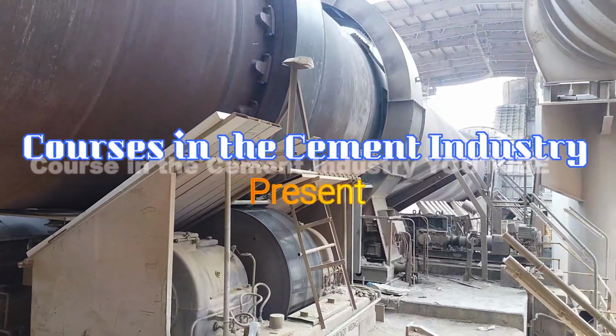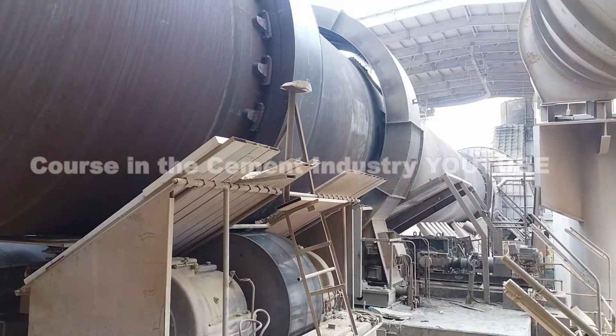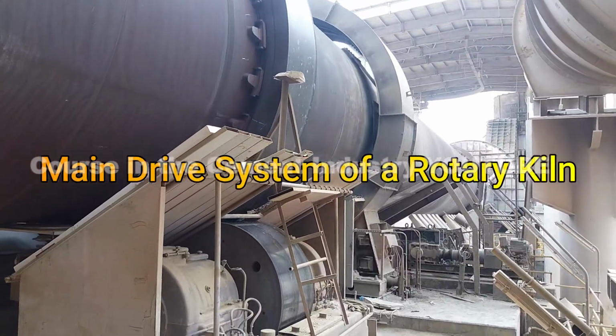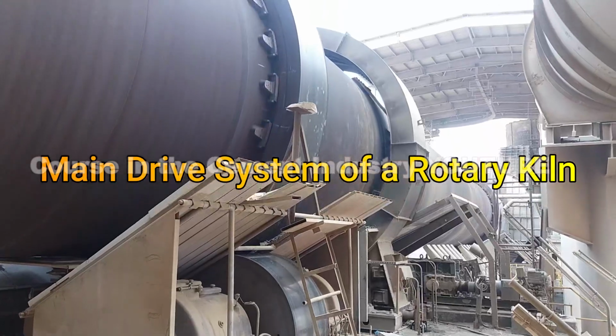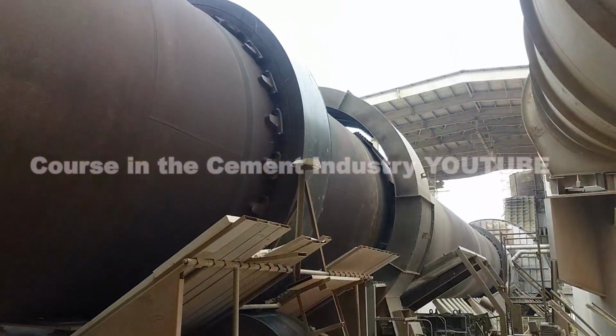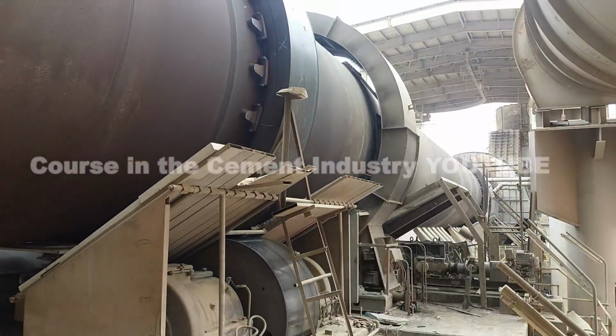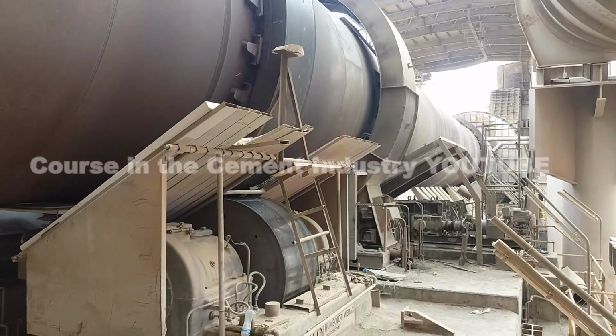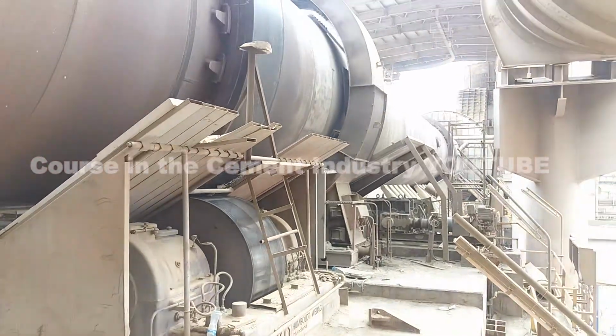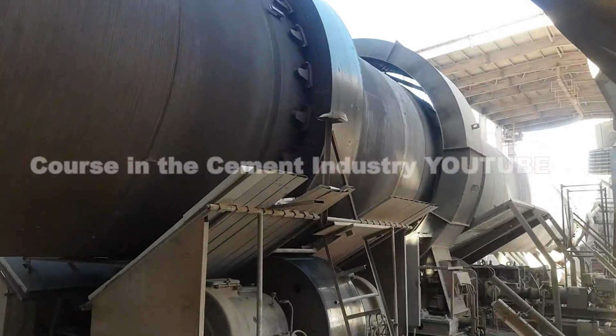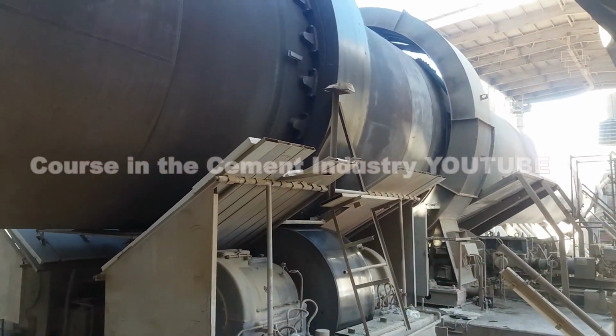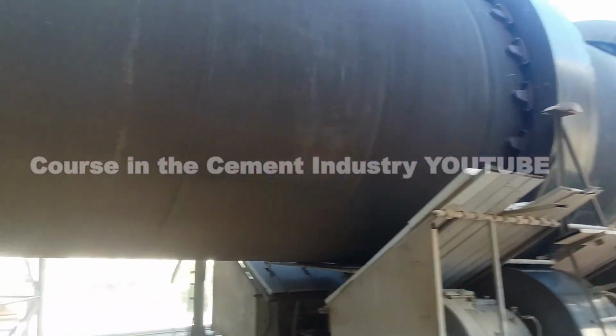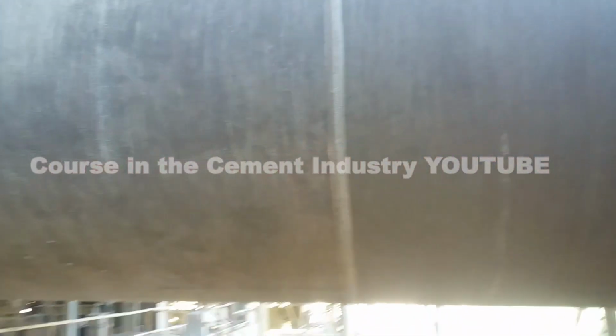This course will explain the main drive system of a rotary kiln. It is the mechanical powerhouse responsible for rotating the rotary kiln shell at a controlled variable speed. Given that a rotary kiln can weigh several thousand tons, including the refractory and material bed, the drive system must provide immense torque while maintaining high precision.